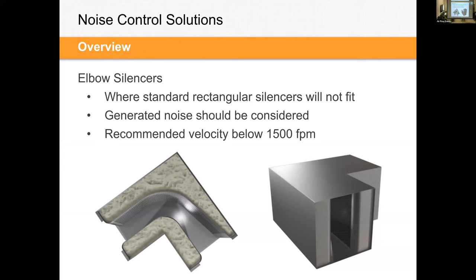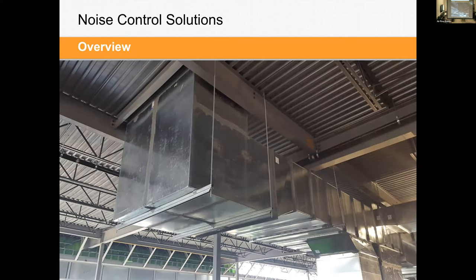Elbow silencers are similar to rectangular ones, except that you're now turning the air 90 degrees, with a radius of curvature to the internal geometry to obtain the directional airflow required. Elbows also work great where you don't have a lot of space. Rectangular silencers take up a specific length of ductwork, so when space is limited, elbows are a great consideration. This is a good example of an elbow silencer.